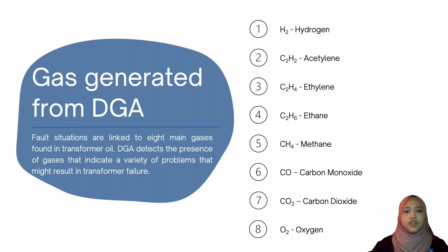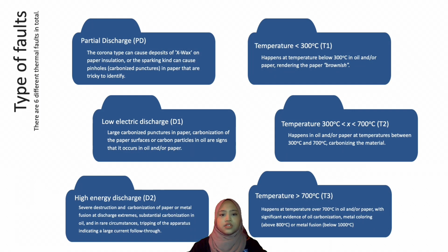Gas generated from DGA. Fault situations are linked to 8 main gases found in transformer oil. DGA detects the presence of gases that indicate a variety of problems that might result in transformer failure. First hydrogen, second acetylene, third ethylene, fourth ethane, fifth methane, sixth carbon monoxide, seventh carbon dioxide, and lastly oxygen. These are 6 different faults in total.